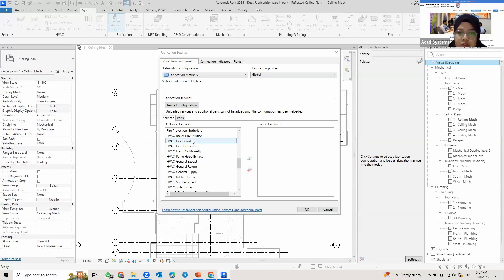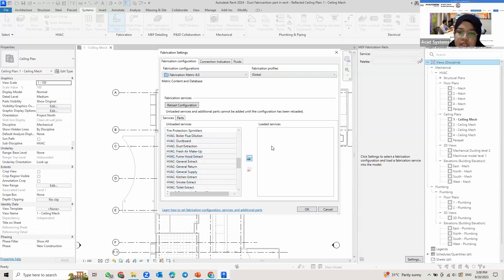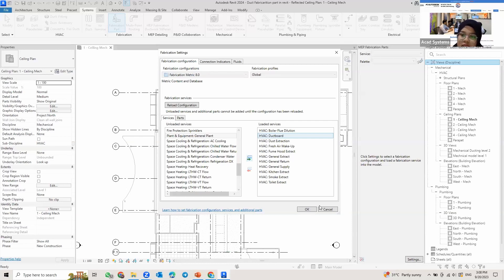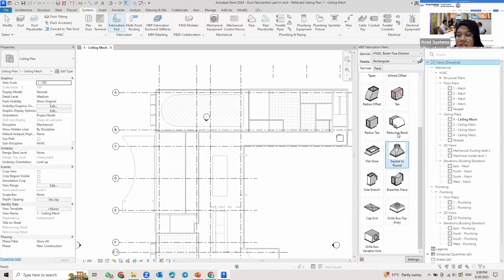To load services into your project, you select what services you want. I'm going to select all the HVAC services here. Then I click on this arrow — there is an add button. Click on that one and it will move them into loaded services. After you change it to loaded services, you click OK. You might need to wait a moment, and then you can see in your services part that the fabrication parts are available to choose.